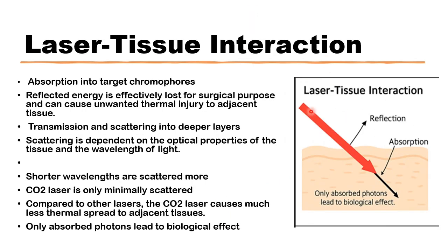Not all the energy delivered by the laser beam will be absorbed by the chromophore, the molecule that is the target of the beam. Some of the energy will be reflected out of the surface, and this will be effectively lost for surgical purposes and can cause unwanted thermal injury to adjacent tissues and sometimes also adjacent individuals.